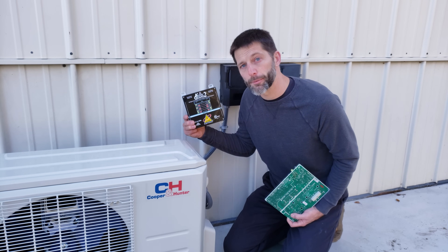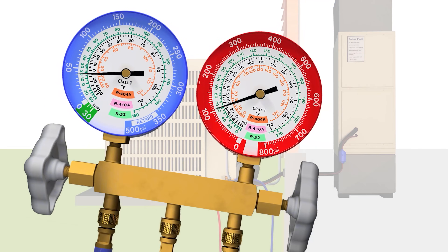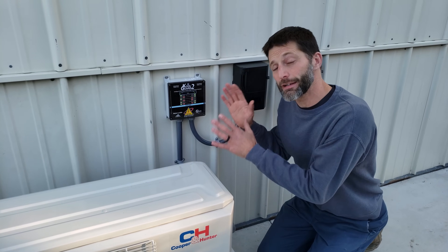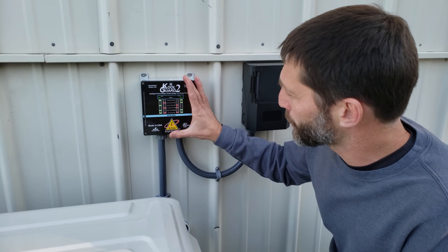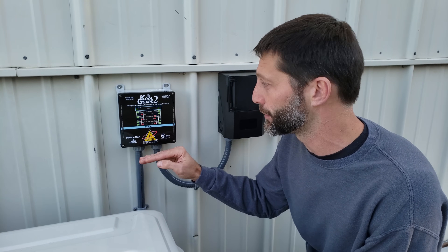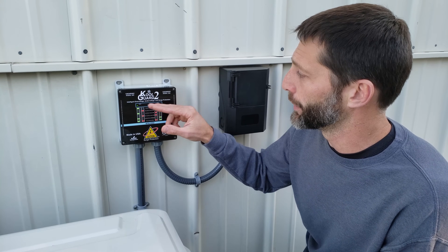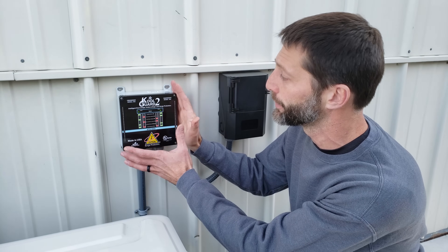We have our Kool Guard 2 already installed. Basically it's acting like a safety switch, monitoring both legs of power. This is 240 volts going through the Kool Guard 2 in series to your mini split, protecting it from low voltage. Anytime one of the two legs goes lower than 104 volts or higher than 130 volts, it's going to shut off both legs and act as a safety switch, also guarding against electrical surges.